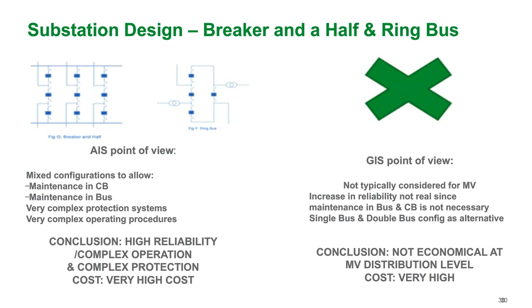So after going through all these, I think you all get the main message is that with GIS, because of its extra reliability and because of its safety and reduced need for maintenance, we can simplify a lot of the complex configurations out there and therefore reduce the cost of a lot of medium voltage substations just by changing the single line to a much simpler design.